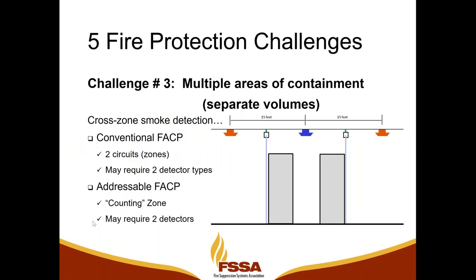With smoke detection, what I mentioned before, cross zoning, another term is counting zoning. For cross zoning, we use that with conventional fire alarm or fire suppression control panels, where we have two zones of detection, and it takes one detector on each zone to activate before we will release the clean agent system into the space. And so when we add aisle containment, we can separate those detectors, and it can take a longer time for smoke to get to detectors on both circuits. So we can have first detection, second detection, and then release.